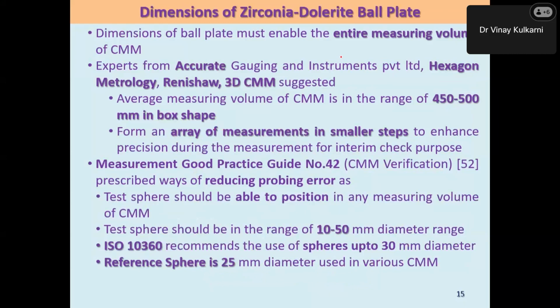So what is the specialty of this ball plate? It covers the entire measuring volume. And I'm very happy to tell you that experts from Accurate Engineering, Hexagon Metrology and Renishaw, we three came together and developed this. The average measuring volume of a CMM is in the range of 450 to 500 mm in box shape. So this box shape, with this array of small steps, we developed as per the CMM verification guide by NPL 42, and at the same time it caters to the needs of ISO 10360 as well.